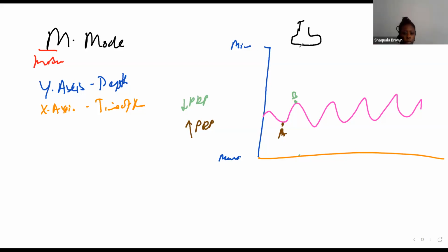Mainly it's because it is something that is moving that we want to look at. That's why, to record M mode, it just uses one pulse. One pulse is going to be used to record your M mode, which is constantly firing at one spot. Things change in that spot constantly, and that change is just recorded over a span of time and shown on a graph.